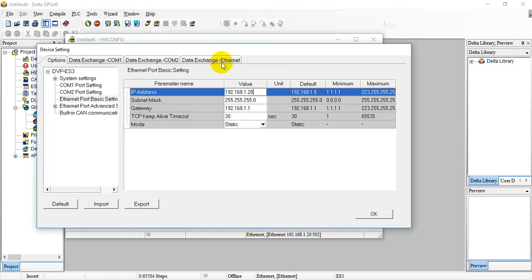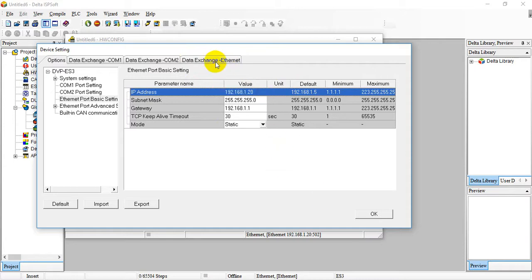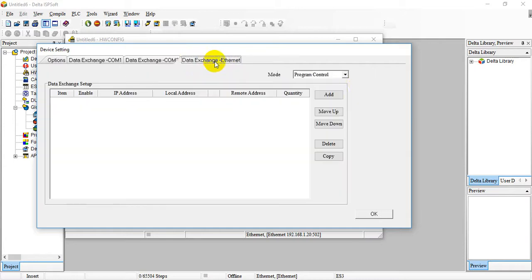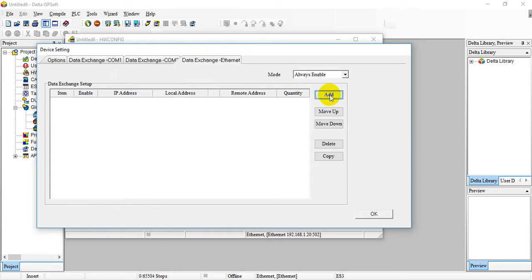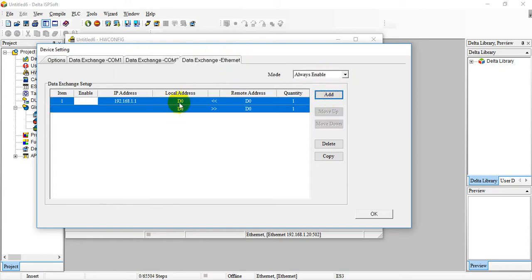Otherwise, when you download the program it becomes 1.5. That means AS200 and ES3 will use the same IP address, which means you will have an IP conflict.